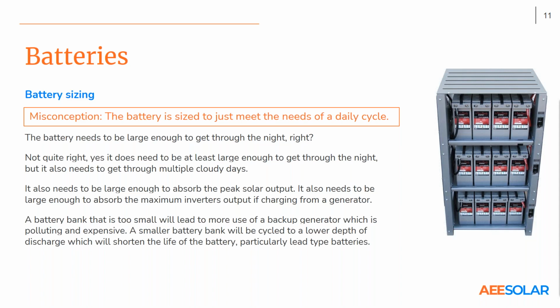Also, that battery bank needs to be big enough to absorb the peak solar production in the middle of the day, or even the inverter capacity that's charging it, so it needs to be a little bit larger than that. It used to be that we'd make them considerably larger, but that's now the most expensive part of the system, so people tend to want to keep that to a minimum. A battery bank that's too small will simply lead to more use of a backup generator, which is polluting and expensive. And that battery bank will also be discharged much more heavily, which reduces its lifetime, particularly with lead type batteries.